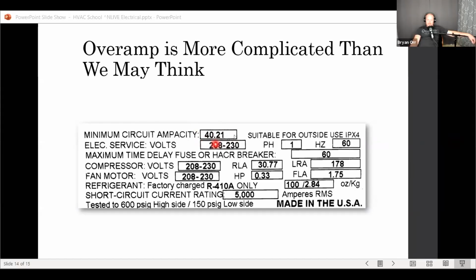So you find a wire that the NEC says, and there's a lot of factors. Okay, so I'm not going to give you all these factors, but if the NEC says that it can carry 40.21 amps under the conditions that you're in, wire length isn't one of them, by the way. That's one people will always say, is that the length of the wire is voltage drop. That's actually not one of the factors that the NEC requires you to consider. Won't go into why that is, but that's actually only a suggestion in the NEC. It mostly has to do with the type of wire it is, the insulation, what the connections are rated for, what the temperature is, and how many wires are running through what they call a raceway. But anyway, that was a lot. You find the wire that's appropriate for this size, and that's the wire you connect.